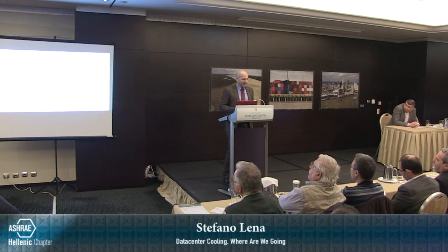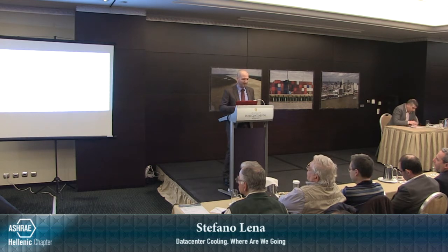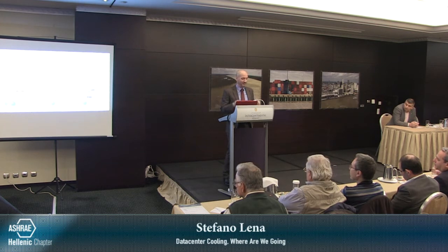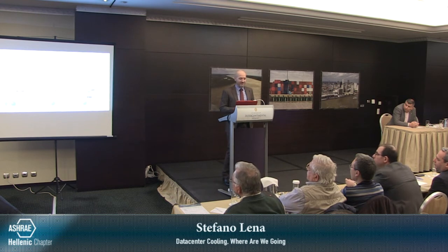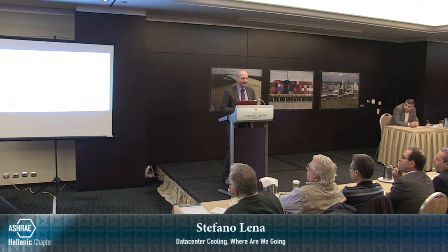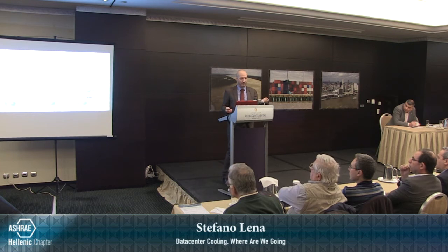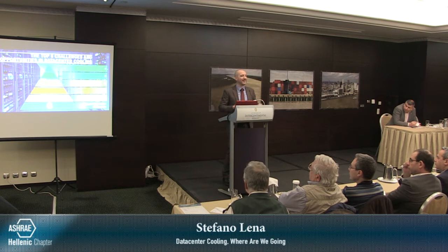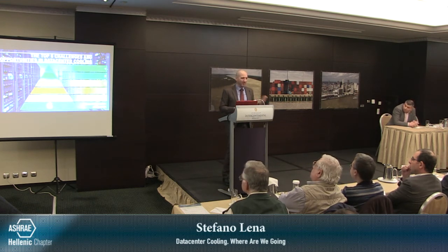Let's mention that there aren't only bad news, but also some good news. There are some technologies that today allow to be compliant with the most severe efficiency standard. For instance, using a variable speed compressor in a chiller today allows to achieve plus 60% of the minimum energy efficiency requirement set for 2021 in the biggest range of cooling capacity for the chillers. So the point is, adopt today the best technology in order to be compliant for the future, because cooling equipment has not the same turnover as the IT equipment. I cannot say that the chiller is for all the time, but for longer than a rack for sure.